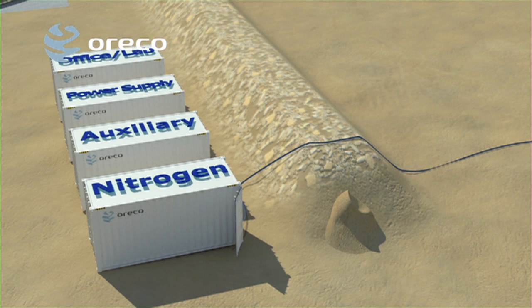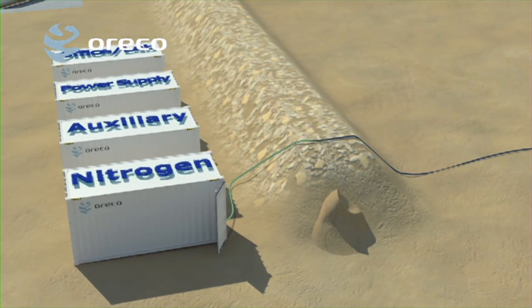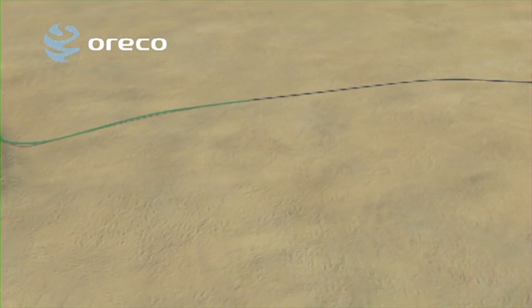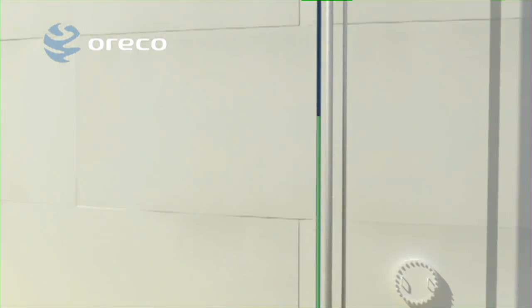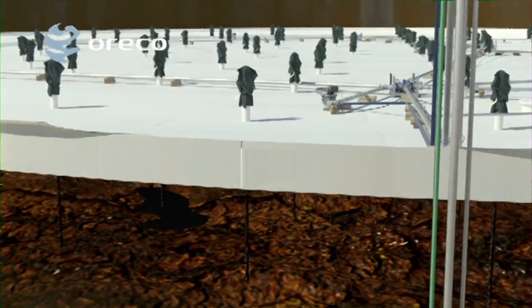To avoid risk of explosion, an inert gas, typically nitrogen, is injected into the tank to reduce the oxygen level to below 8%. This level is maintained throughout the entire tank cleaning process.